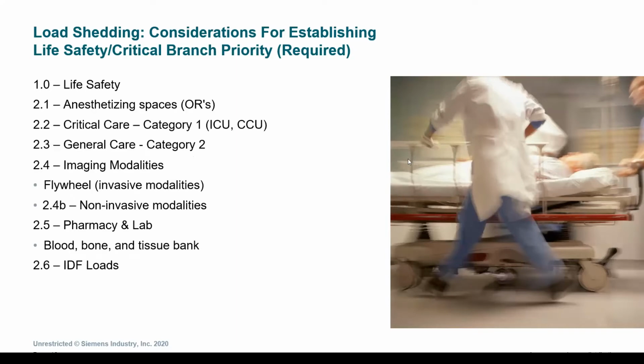Critical being priority 2. And we look at the critical branch, we start with the highest priority of the critical branch, starting with the spaces serving the highest level of acuity. So first, the transfer switches serving anything within the anesthesia spaces, such as the ORs. It's important to mention that a critical branch transfer switch could serve multiple different spaces, such as the ORs or a piece of imaging equipment. In this case, it's important that all of the feeders from that transfer switch are designated by their highest level of acuity, in which case that example would be classified under the anesthesia and therefore part of the 2.1 proposed priority.